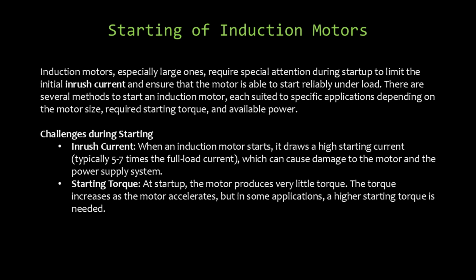Starting an induction motor presents unique challenges. During startup, motors draw a significantly high current, typically 5 to 7 times the full load current. This inrush current can potentially damage the motor and power supply system. Moreover, motors produce minimal torque at startup, with torque increasing as the motor accelerates. For some applications, achieving higher starting torque becomes crucial.